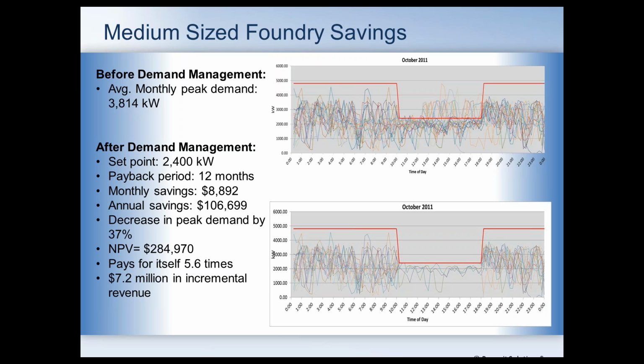That small foundry was operating 4 different power supplies that were down in the 200 to 250 kW range. This facility is a medium-sized facility. There again, you can see they had an on-peak, off-peak time period. Their on-peak started roughly at 10 o'clock in the morning and went to 1800 in the afternoon. You can see the number of occurrences where they were spiking above a set point that they wanted to operate at. Once the automated system was in, it kept them down and kept it depressed during that on-peak time period to give them some significant savings. Next slide, please.